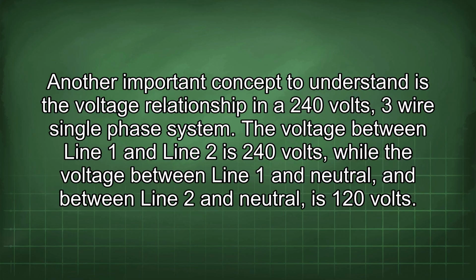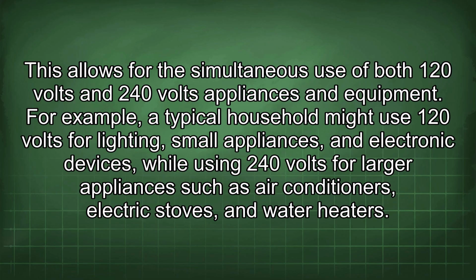Another important concept to understand is the voltage relationship in a 240 volt, 3-wire single-phase system. The voltage between line 1 and line 2 is 240 volts, while the voltage between line 1 and neutral and between line 2 and neutral is 120 volts. This allows for the simultaneous use of both 120 volt and 240 volt appliances and equipment. For example, a typical household might use 120 volts for lighting, small appliances, and electronic devices, while using 240 volts for larger appliances such as air conditioners, electric stoves, and water heaters.